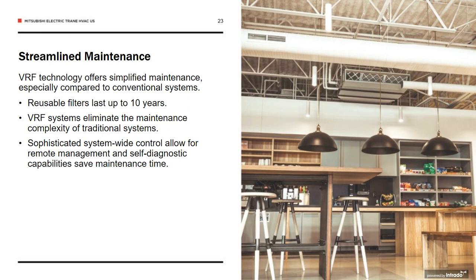While maintenance associated with owning a building is inherent, it doesn't have to be a financial burden and a time waster, right? VRF offers simplified maintenance via reusable filters that can last up to 10 years. And the onboard diagnostics and monitoring also allow you to control the system and monitor system-wide what's going on with the system at any given time. This allows for easier maintenance time to maximize your operational costs.